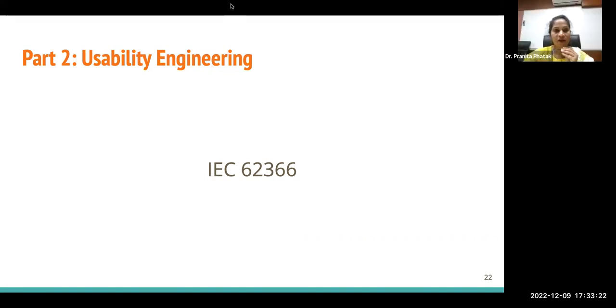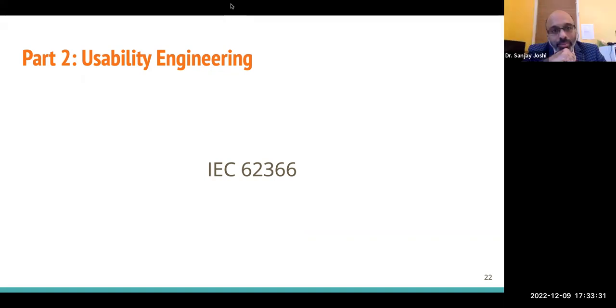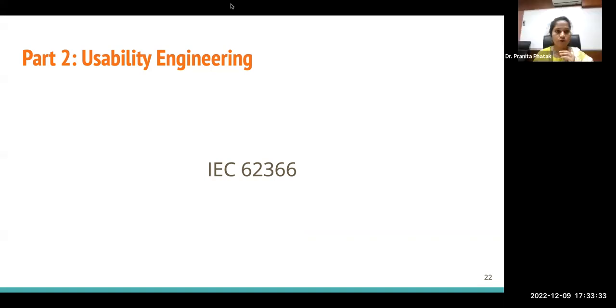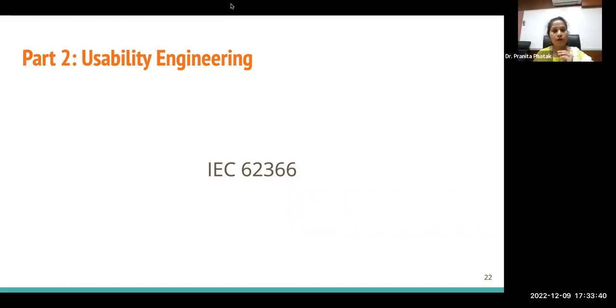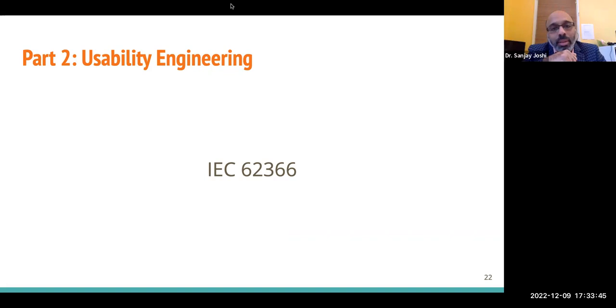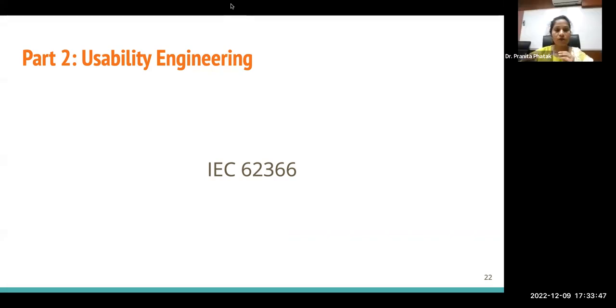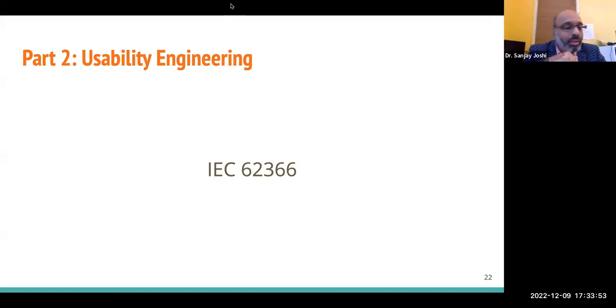Okay. On that line, I would like to ask you one question. ISO 13485 is for the organization. Yes. And risk management is basically per product. So for each device, for each product that you are making. Yes, each device. So every time a startup makes a new device, or even if they do some alteration or tweak something, that also needs some kind of risk process to go through again?